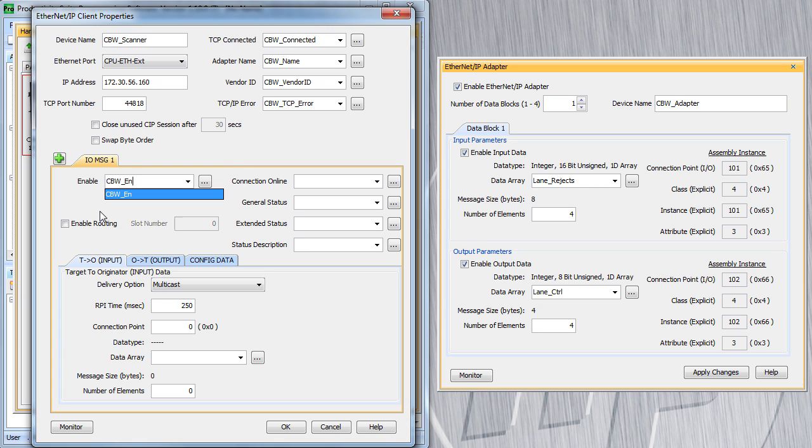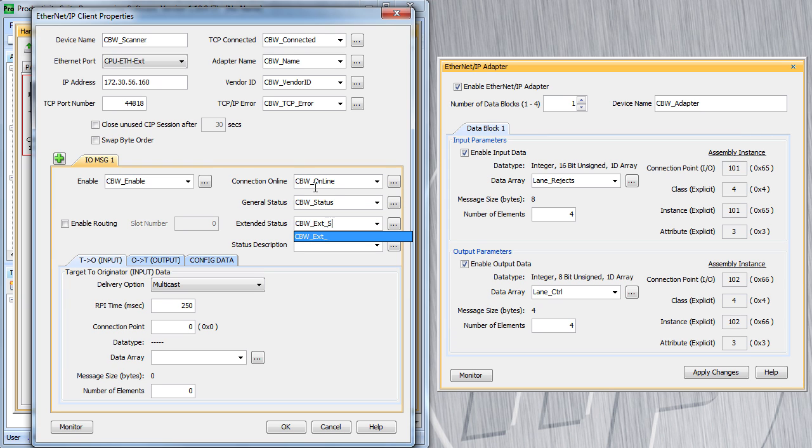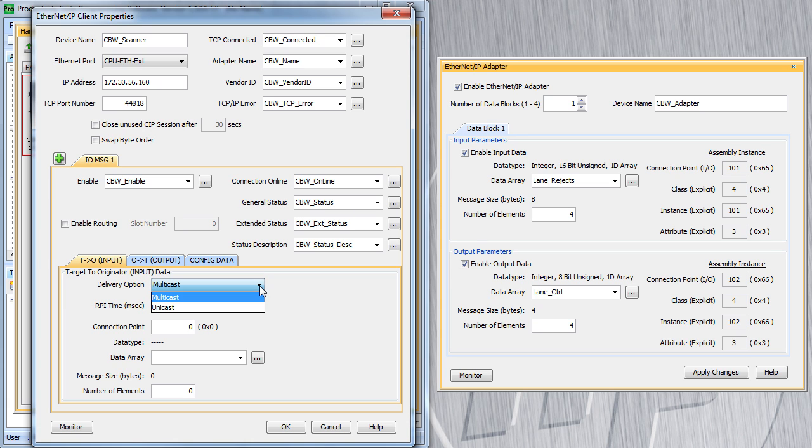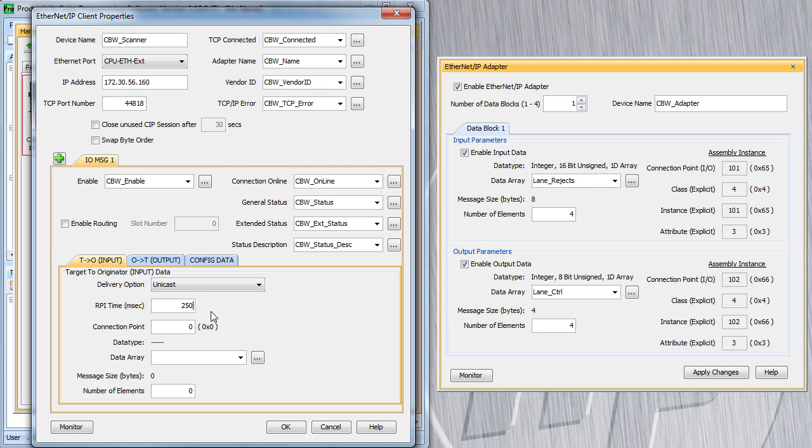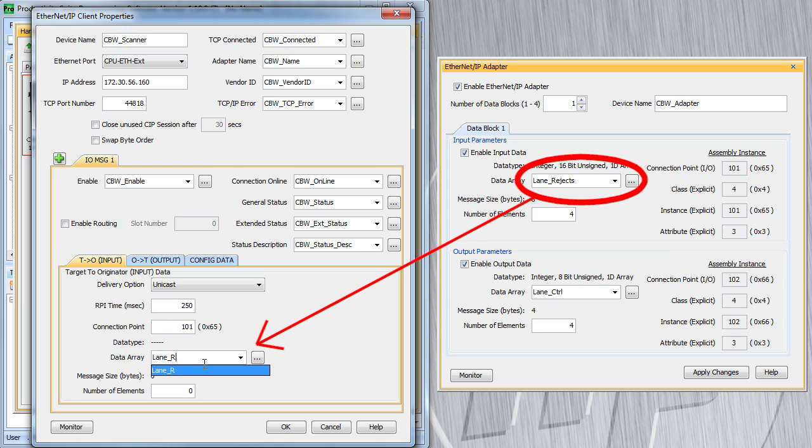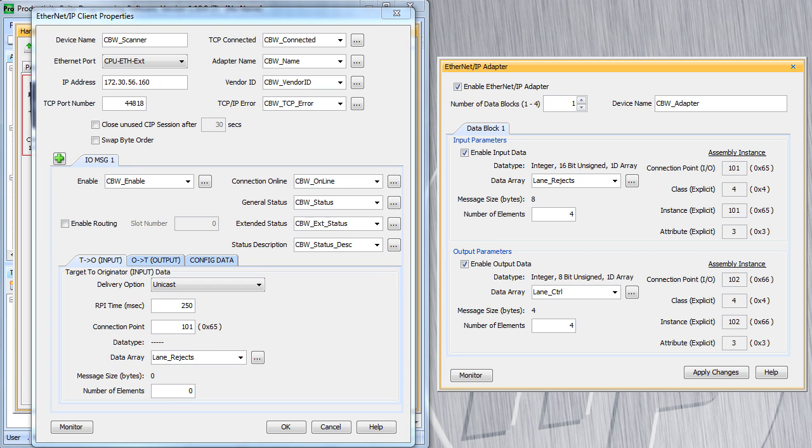I am going to go ahead and fill in these tags over here so we can monitor the status of the scanner. And then once that is done, all we have to do is configure the messaging from the target to the originator – that's from the candy bar wrapper machine to us, so that's our input – and from the originator to the target – that's us to the candy bar wrapping machine which is our output. For the data coming to us, we want that to be delivered by the adapter in a unicast just to us. The interval between messages is currently set to 250 milliseconds – that's 4 times a second – that's plenty, I'll leave that alone. This connection point, we take that straight from the adapter. This is the input data, so we go to the input block and we see that our connection point is 101 – so that's the number we put right here. Now we need to create a data array for those results to be put in. I like to use the same name as the data array that is down on the adapter so there is no confusion.